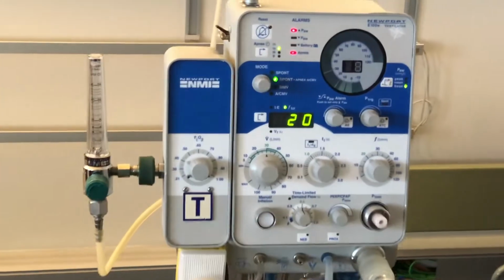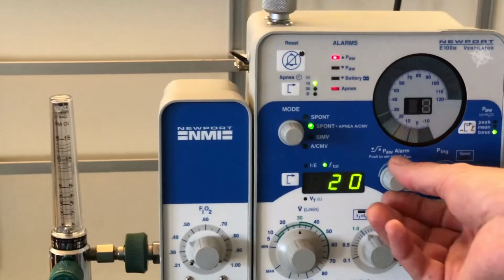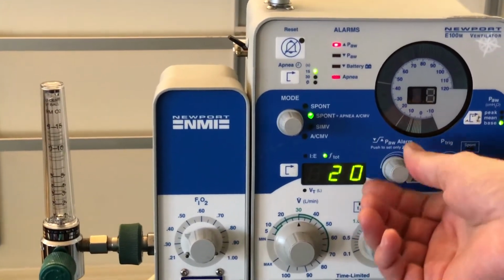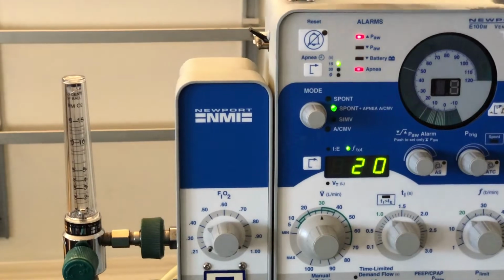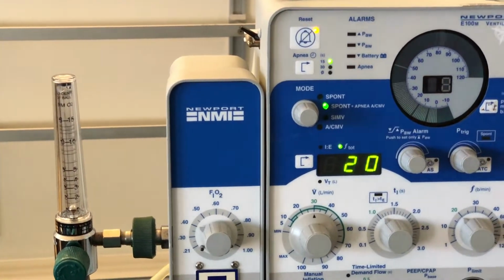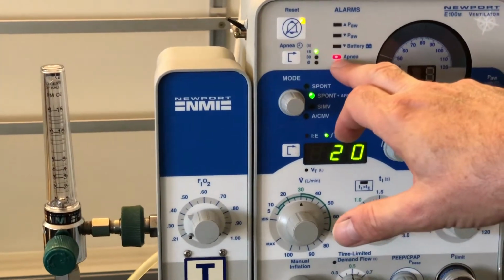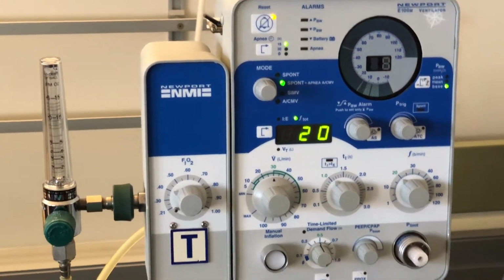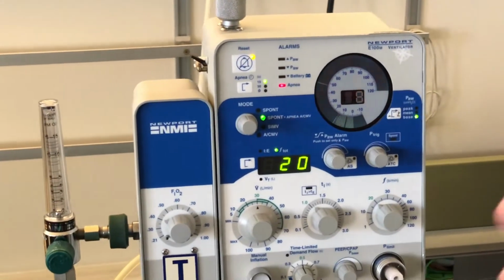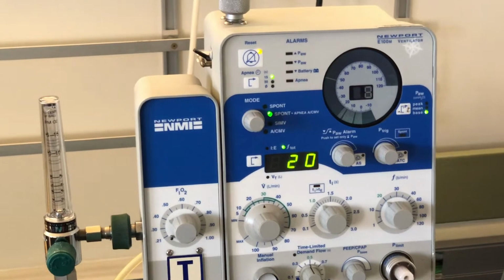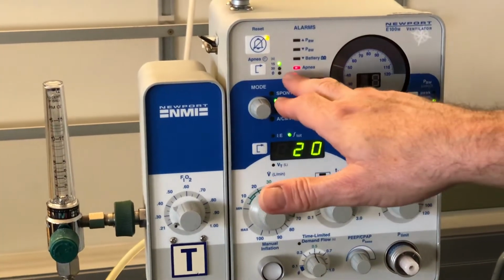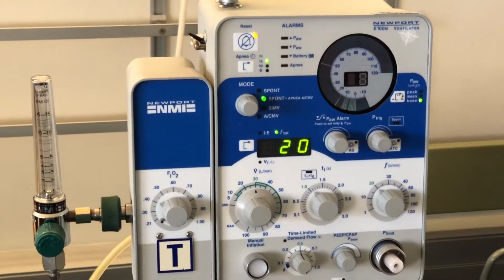There the apnea alarm goes. You can see it's flashing. I'm just going to adjust the upper pressure airway limit. And I'm going to silence the alarm. But clearly you can see that the apnea light is flashing continuously and the machine remains in the apnea backup mode. To be able to take that alarm away, the patient needs to breathe.